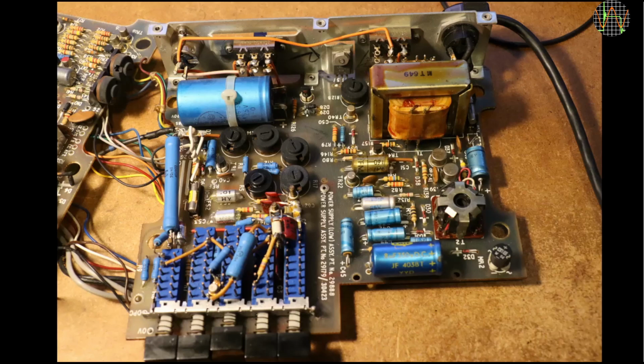It contains the 5 range switches. In this picture they are from left to right for the 2000, 200, 20, 2 and 0.2 ranges. Behind the range switches is part of the input attenuation. The round black things are some of the calibration potentiometers. The rest of this board is the power supply. You can see the mains transformer and the big smoothing cap.